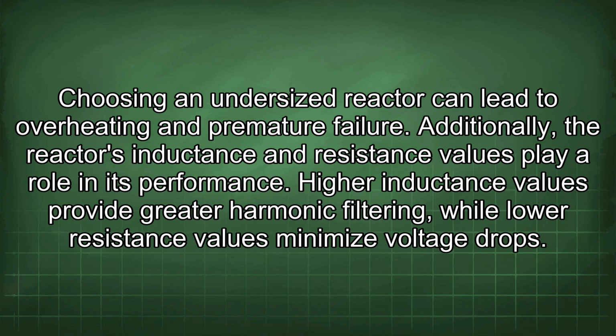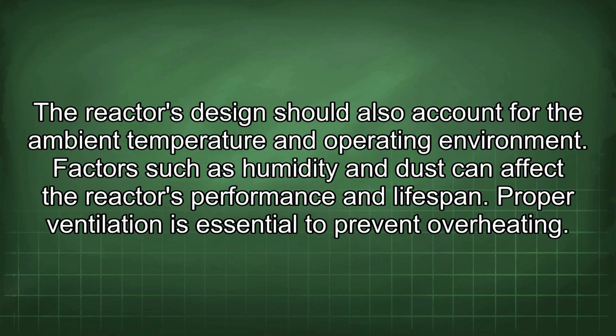Additionally, the reactor's inductance and resistance values play a role in its performance. Higher inductance values provide greater harmonic filtering, while lower resistance values minimize voltage drops. The reactor's design should also account for the ambient temperature and operating environment. Factors such as humidity and dust can affect the reactor's performance and lifespan. Proper ventilation is essential to prevent overheating.